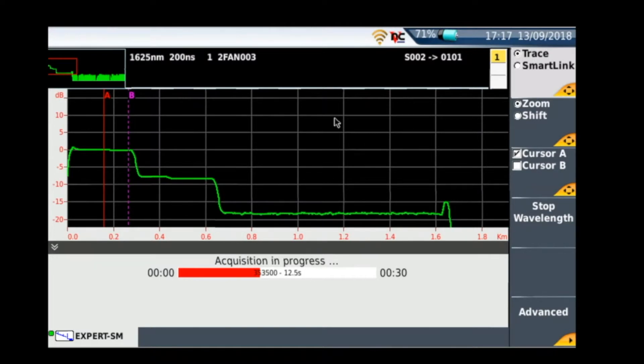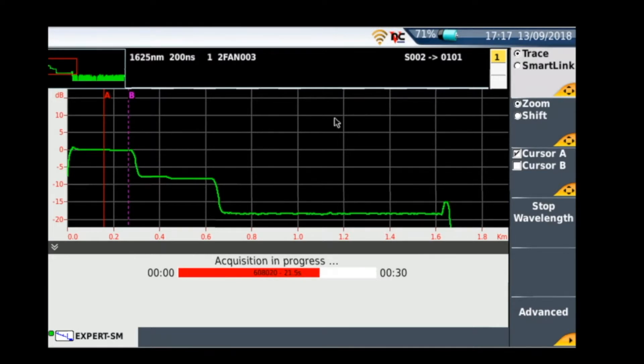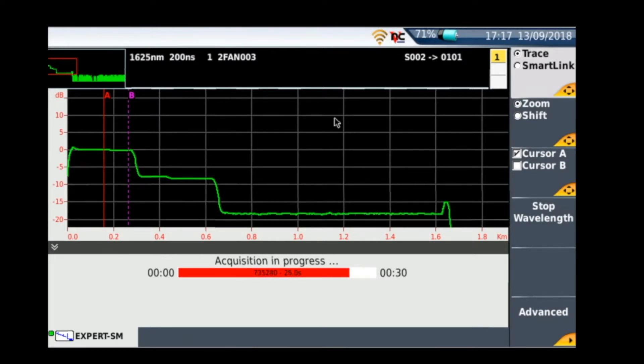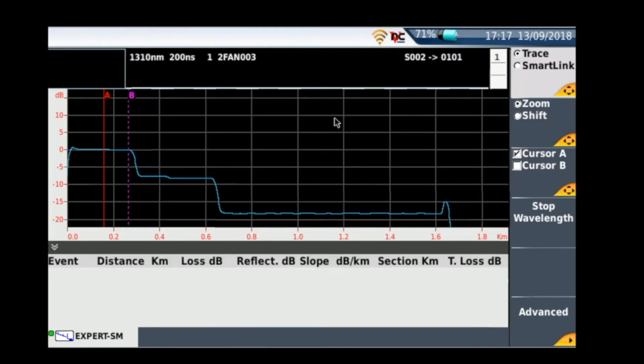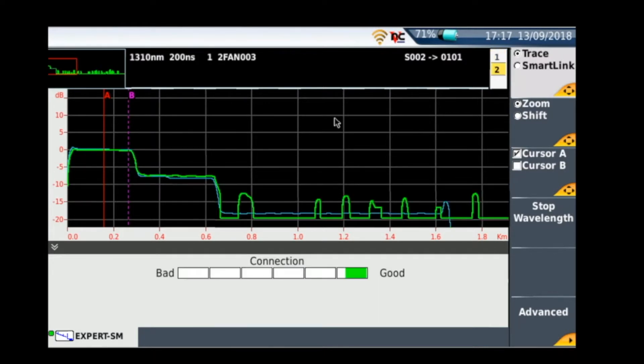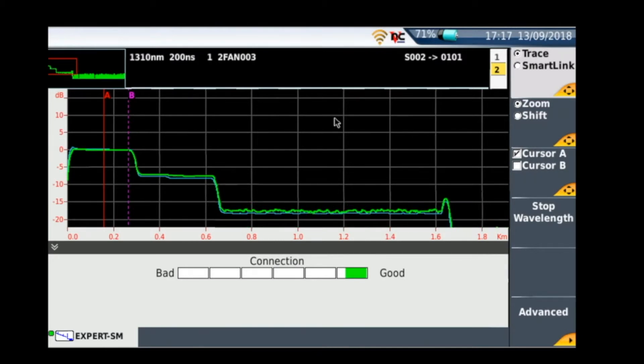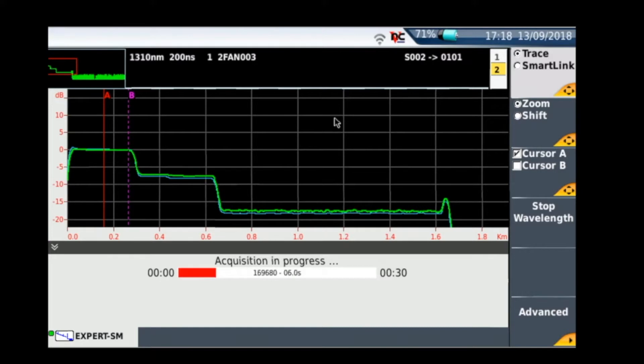So it's going to do a 30 second trace on each wavelength on 1310 and 1625 nanometers. And while it's doing that I'll just explain what you can see on the screen. So in the far left hand corner you see a small rectangle with a very scaled down version of the trace. And within that you see a red rectangle. Now that red rectangle can be zoomed in or out and that affects what you see on the main display. To the right of that you can see the wavelength that it's testing on, you see the pulse width that it's set to, you see the fiber number and the FAN ID.